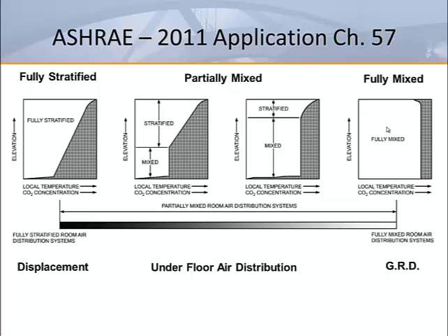A partially mixed system, such as an underfloor system, where air is introduced through the floor from the plenum below, will mix the lower occupied area and stratify the upper zone. As illustrated, the height of the mixed area may vary depending on the height of the conditioned plume.